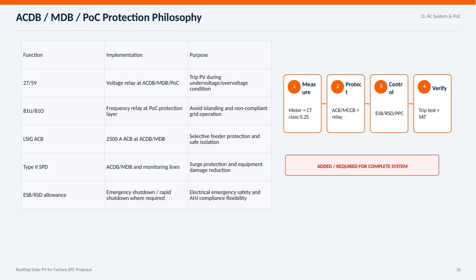Here, we're looking at the protection philosophy for the ACDB, MDB, and point of connection in our rooftop solar PV system for the factory EPC proposal. The key functions include voltage relays like 27 and 59, which protect by tripping the PV during undervoltage or overvoltage conditions. Frequency relays 81U and 81O are critical to prevent islanding and ensure the grid operates compliantly. We also have a 2,500 ampere air circuit breaker at the ACDB or MDB to provide selective feeder protection and safe isolation. Surge protection is handled by Type 2 SPDs to reduce equipment damage, while the ESB and RSD provide emergency shutdown capabilities to meet safety requirements and AHJ compliance.